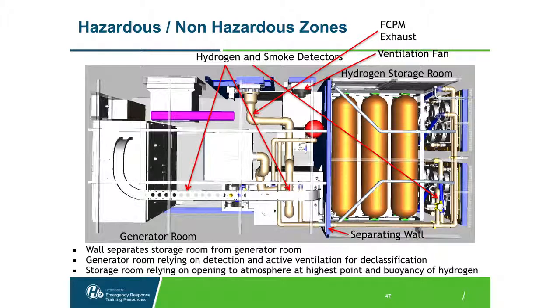Smoke and hydrogen detectors. There is 1 hydrogen sensor in the storage room, kind of a redundant safety factor because it's open to atmosphere, with lots of passive ventilation. And the way it's designed, it also keeps hydrogen from accumulating in this room. In the generator room, we have 2 hydrogen sensors and a smoke detector. There's active ventilation in the generator room. And this wall here separates the storage from the generator room.